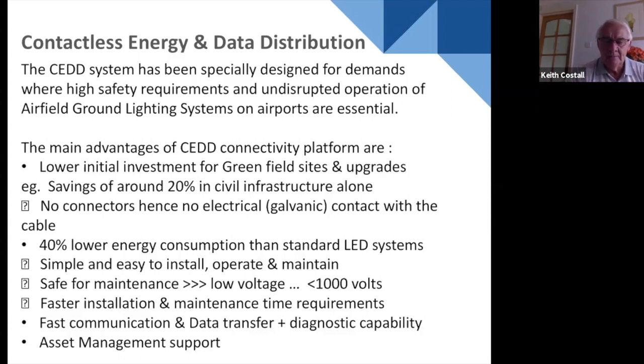Therefore, if you don't have infrastructure such as transformer pits, it's relatively easier to install. And importantly, from a safety viewpoint—remember safety is a major issue for us in traditional AGL—the voltage on the system is below 1000 volts, so it takes us out of the high voltage safe working procedures regime and we don't have to go through that authorized person scenario.